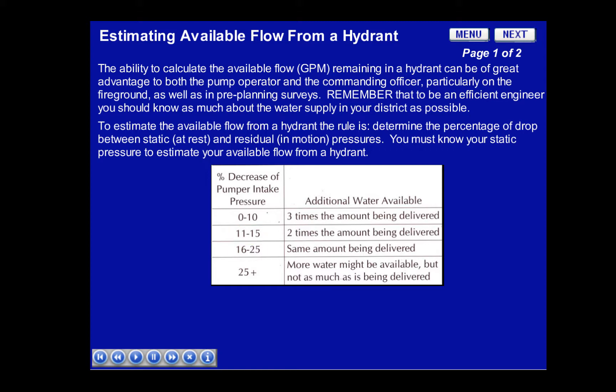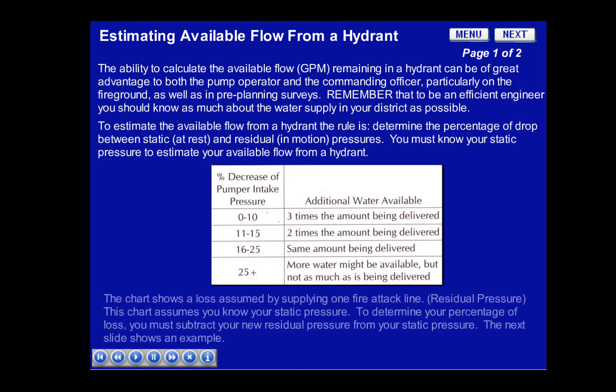And if you have a loss between 16% and 25%, you will be able to deliver the same amount of water through your original line. If you have a loss greater than 25%, more water might be available, but not as much as being delivered. The chart shows a loss assumed by supplying one fire attack line, which will mean your residual pressure. This chart assumes you already know your static pressure.